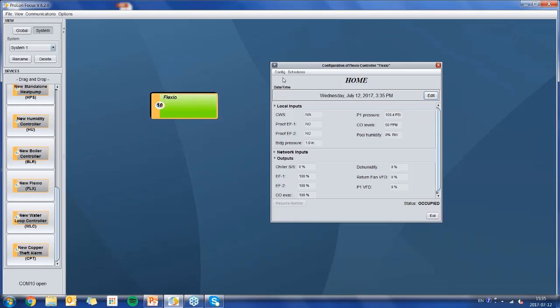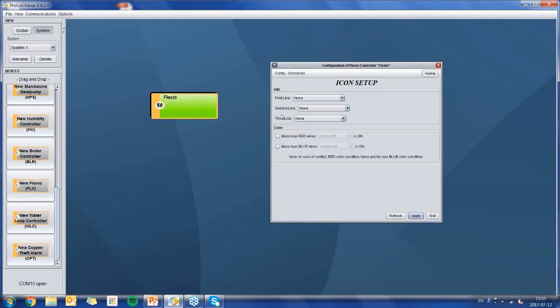Our icons are usually one of 3 different colors: green, blue, or red. In this case we can choose what color goes with what. So I could say make the icon red if ever my evacuation sequence for the carbon monoxide is on, and make it blue essentially when my chiller is on. We could just leave it like that, but you guys can choose. And here we have a note in case the icon wants to be red and blue at the same time: the red color will take priority over the blue color.